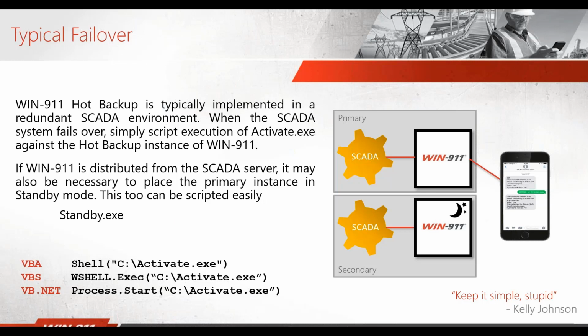Win911 is typically implemented in a redundant SCADA environment. So when the SCADA system fails over, you can have a simple script that runs the activate executable and fails over with your SCADA system. As your primary SCADA system fails over to your secondary SCADA system, you can have Win911 follow that and be in sync with your SCADA system.